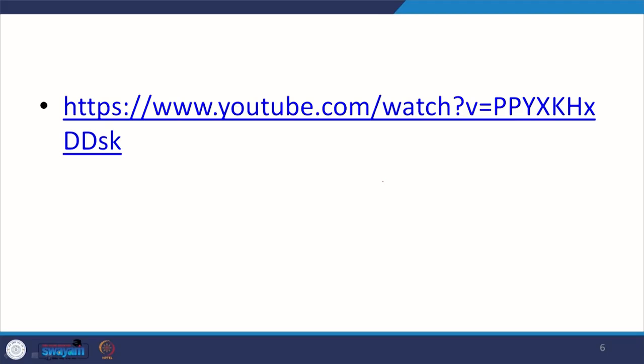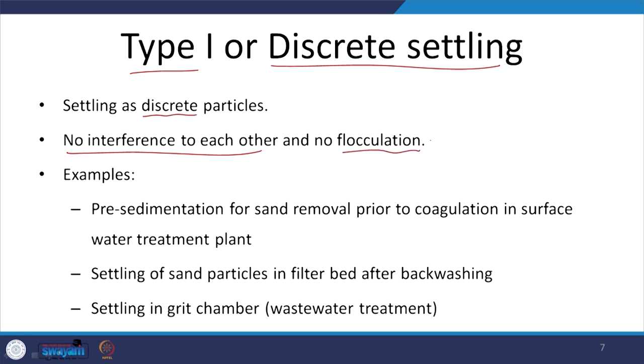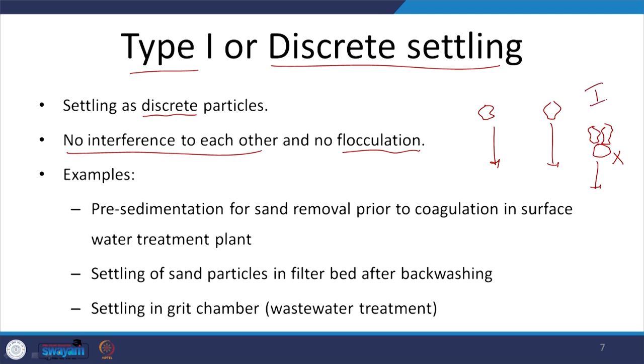The types of settling discussed until now were mostly Type 2. For Type 1 or discrete settling, the major aspects are: particles do not interact with each other and settle as discrete particles — no flocs are formed. This occurs in pre-sedimentation for sand or grit removal, prior to coagulation in surface water plants, and in a grit chamber of the wastewater treatment plant, as mentioned earlier.